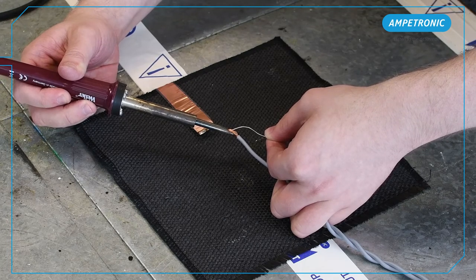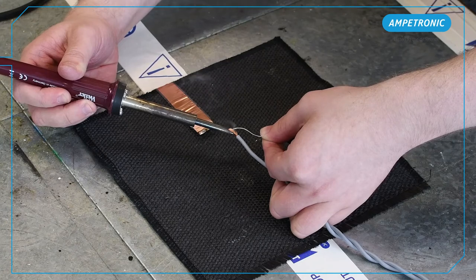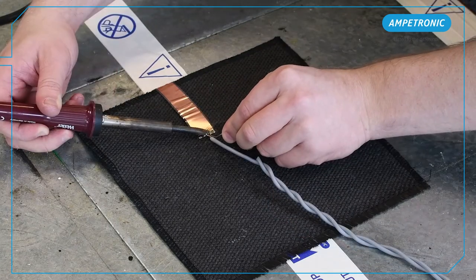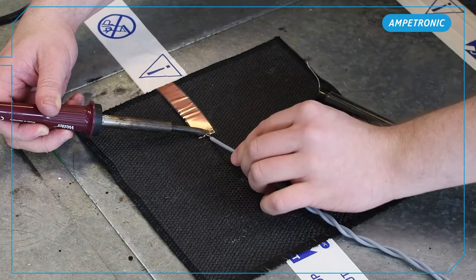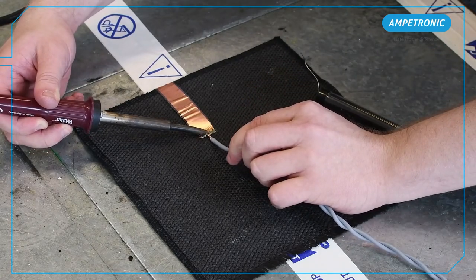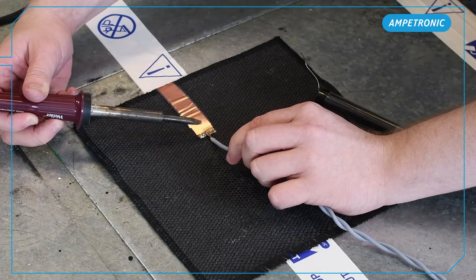You start by either tinning the flat copper tape or the feed cable. In this case, I started by tinning the flat copper tape first and then the feed cable. When joining the cables, make sure you have a decent amount of overlap between the two cables and then apply heat.